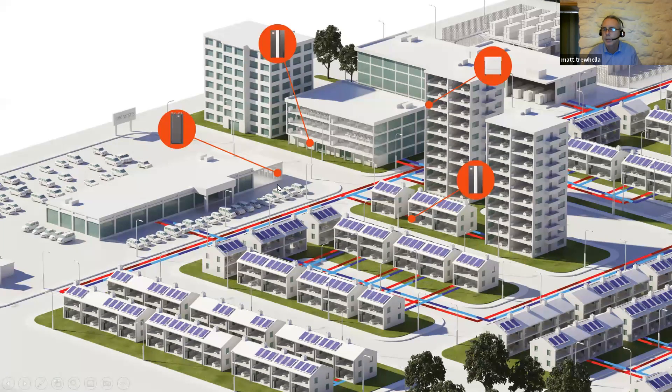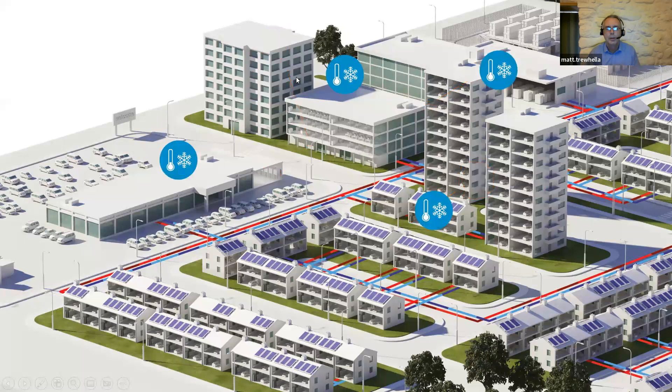There's no central billing mechanism or plant — just when a heat pump turns on, its pump turns on and it exchanges energy with the network. You can also do cooling off the same network: 10 degrees is a great input temperature for both heating and cooling. A supermarket in summer is trying to take cold from 25–30 degree air for its freezers and fridges, and in winter trying to heat areas from 0–5 degree air. With this network, it takes both from that mid-temperature, and the waste heat from cooling goes back into the network.